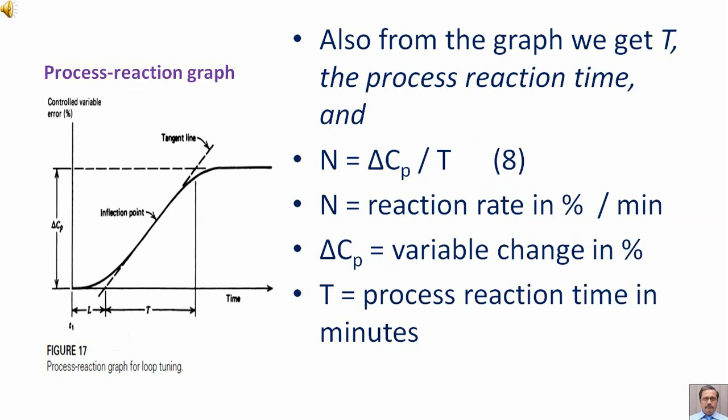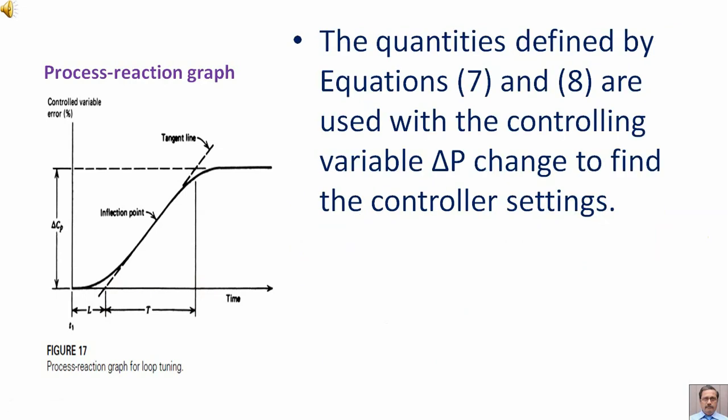Also from the graph we get capital T, the process reaction time, and capital N equal to delta C subscript P divided by capital T. Equation 8: N is the response rate in percent per minute. The quantities defined by equations 7 and 8 are used with the controlling variable delta P change to find the controller settings.